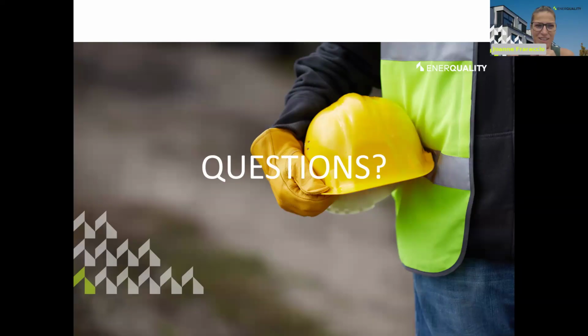Fair enough. Okay. Joss had a question. Is connecting to the cold water side of the mixing valve also common in Canada, or to both the cold water side of the mixing valve and the hot water supply? Yeah, we don't recommend doing that because the temperature is variable, and the mixing valve flow rate changes quite a bit during the year. So you have a problem with how much water is going into the coil of the heat exchanger going into the cold side of the mixing valve. That flow rate varies quite a bit, and that reduces the performance. So it's not recommended to do that.